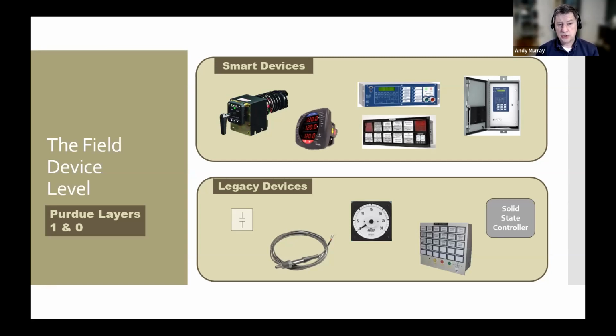Not only could you use the handle to operate the device mechanically, but we may be able to send it signals to say we need you to open, and the switch will open through messaging. You may also have meters that connect to the electric system, monitor the voltage and currents, and then translate those into a protocol that comes down across the SCADA system.